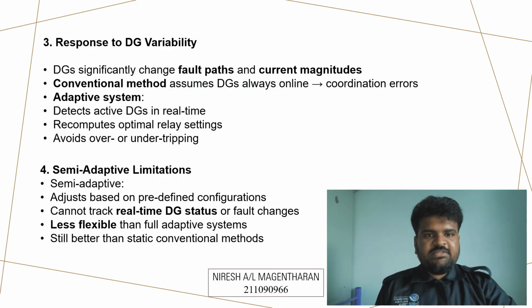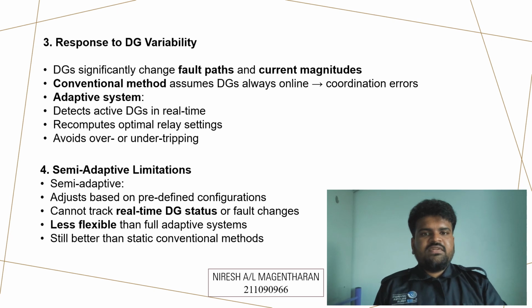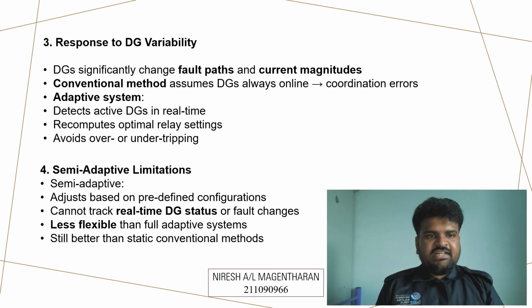So the third point is response to DG variability. DGs significantly change fault paths and current magnitudes. Conventional method assumes DGs always online, which causes coordination errors. Adaptive system detects active DGs in real time, recomputes optimal relay settings, avoids over or under tripping. The fourth point is semi-adaptive limitations. Semi-adaptive adjusts based on predefined configurations but cannot track real-time DG status or fault changes, less flexible than full adaptive systems but still better than static conventional methods.